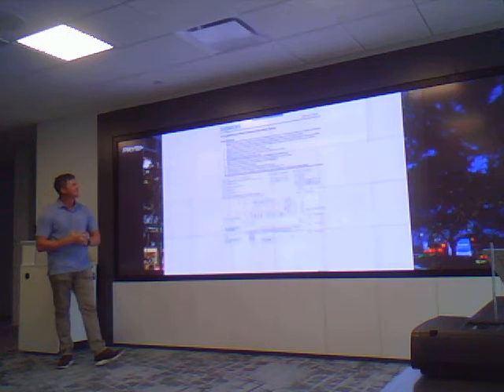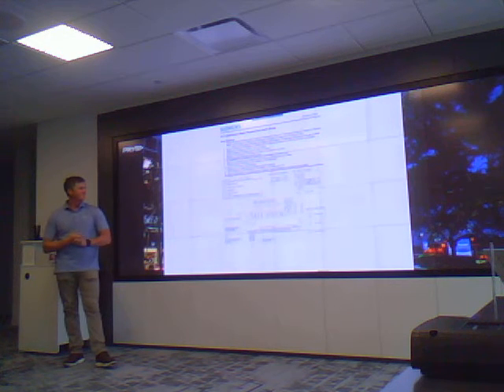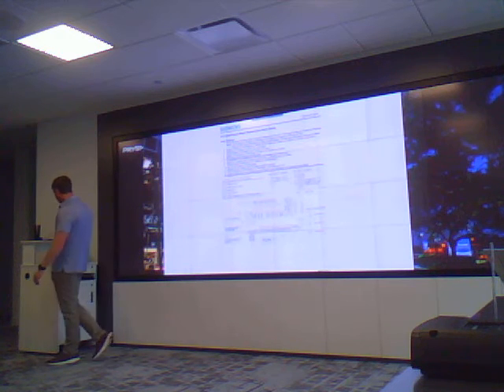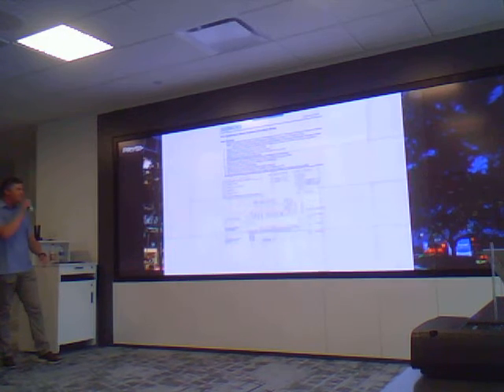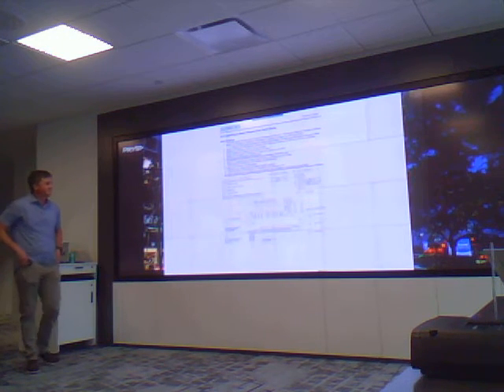So this is the I/O board. They're calling this the replacement install guide. This is a step-by-step on how to replace a bad I/O board, okay, that's all it is. And if you see in red down below, it shows you for this site where all the jumpers are supposed to be set. In red, it's right there in front of your face. Change the jumpers, because you'll start testing and go, well, that ain't right. Then you realize the jumper's wrong. That's about the name of that tune.